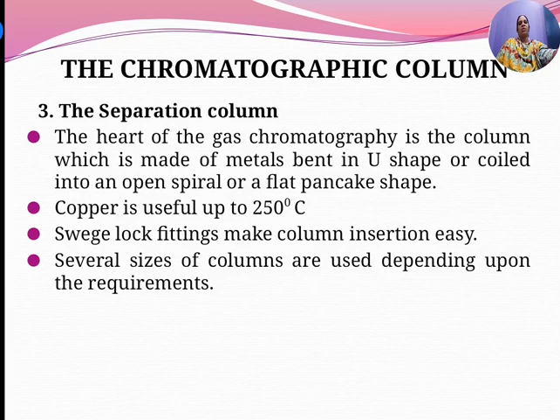So the heart of the gas chromatography is a separation column, or the chromatographic column, which is made of metal bent in a U shape or coiled into an open spiral or a flat pancake shape. Copper is useful up to 250 degrees centigrade. We have Swege lock fittings which make column insertion easy. Depending upon our requirement, several sizes of columns are used. So this is the heart of the gas chromatography.